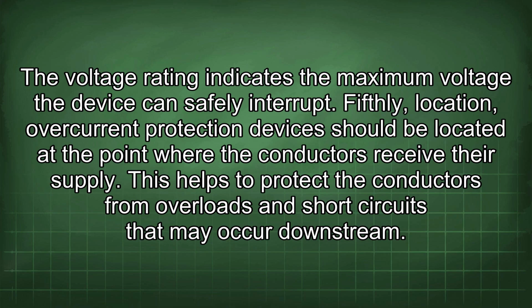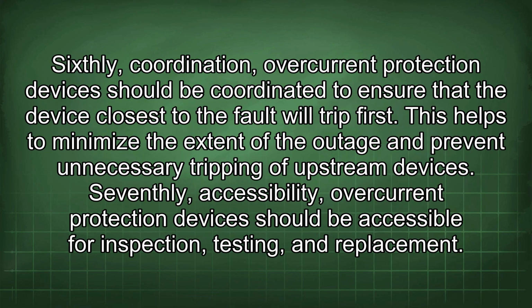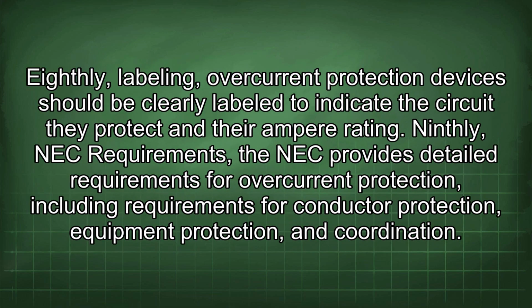Fifthly, location. Overcurrent protection devices should be located at the point where the conductors receive their supply. This helps to protect the conductors from overloads and short circuits that may occur downstream. Sixthly, coordination. Overcurrent protection devices should be coordinated to ensure that the device closest to the fault will trip first. This helps to minimize the extent of the outage and prevent unnecessary tripping of upstream devices. Seventhly, accessibility. Overcurrent protection devices should be accessible for inspection, testing, and replacement. Eighthly, labeling. Overcurrent protection devices should be clearly labeled to indicate the circuit they protect and their ampere rating.